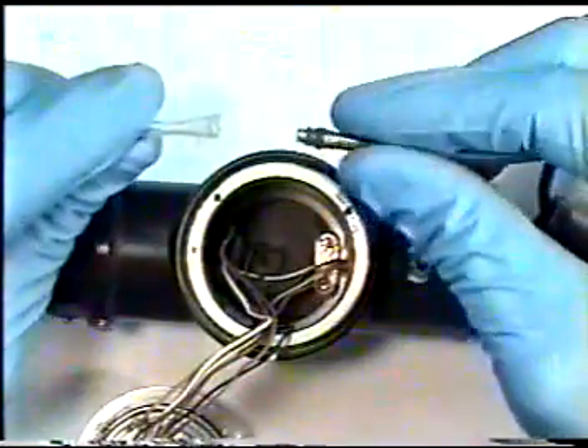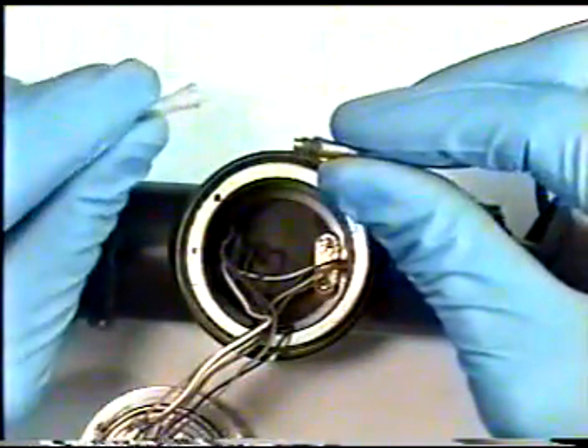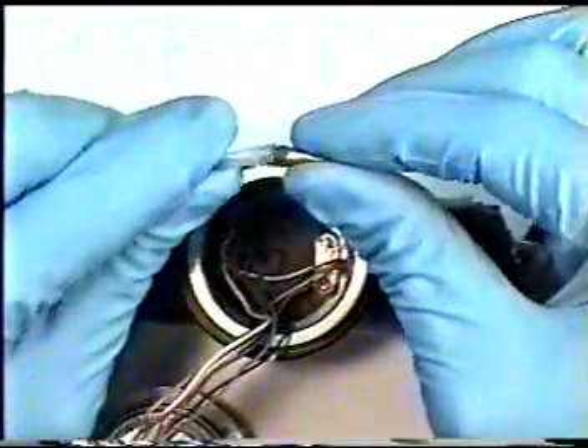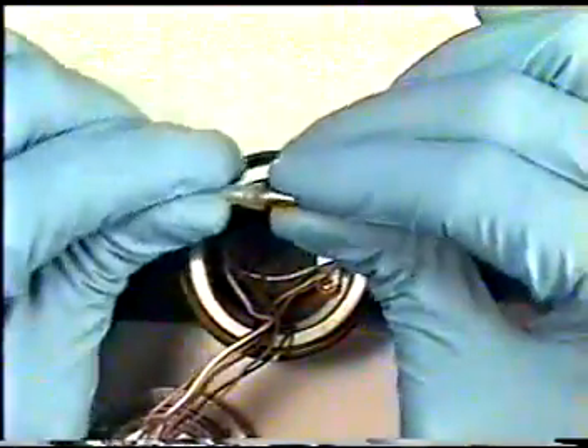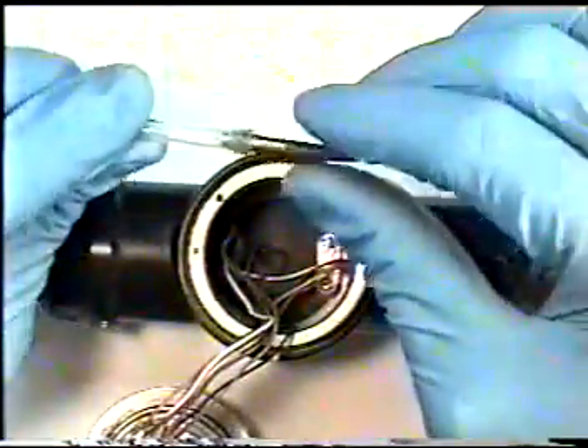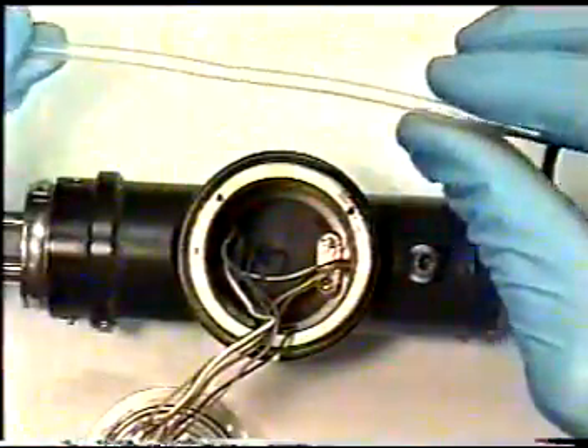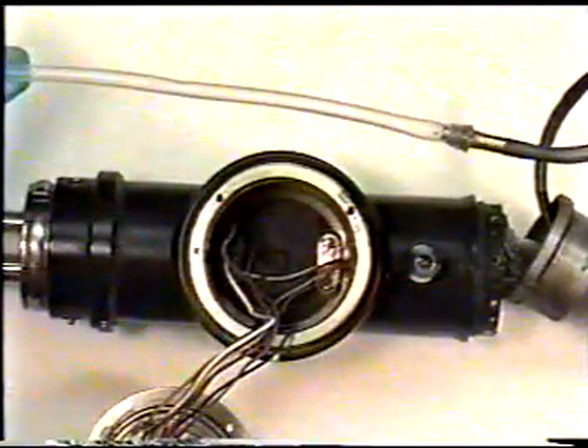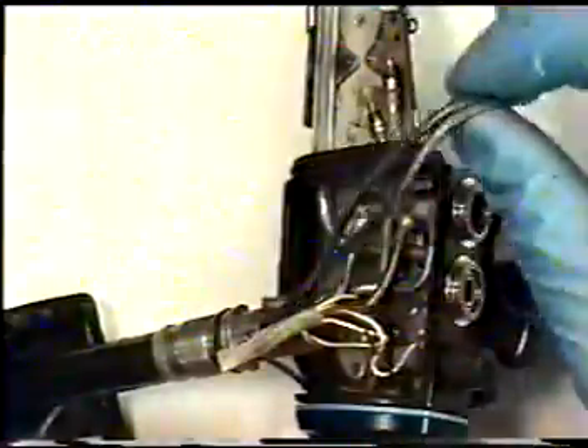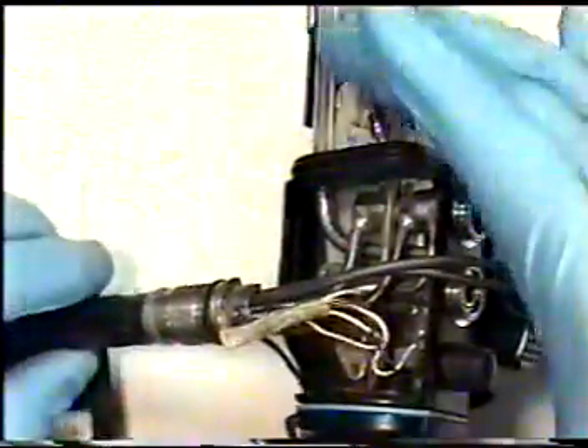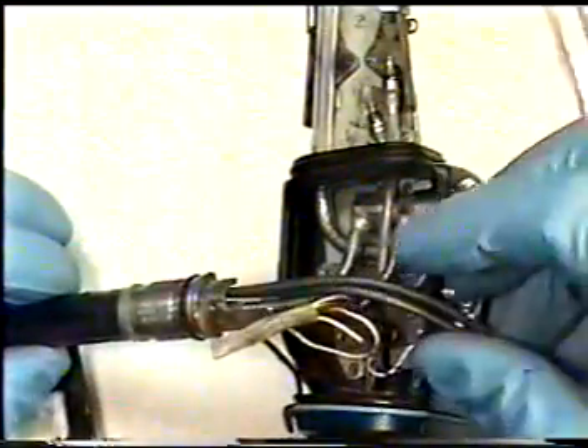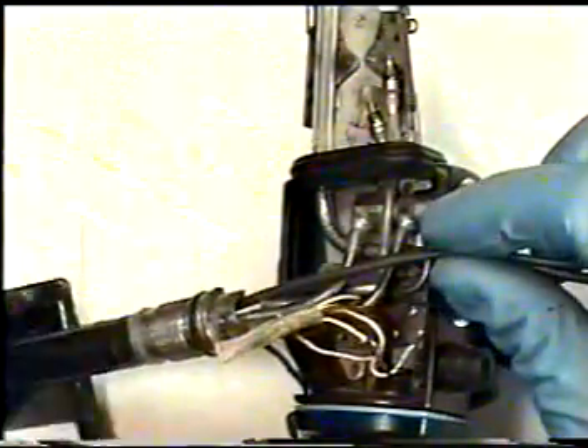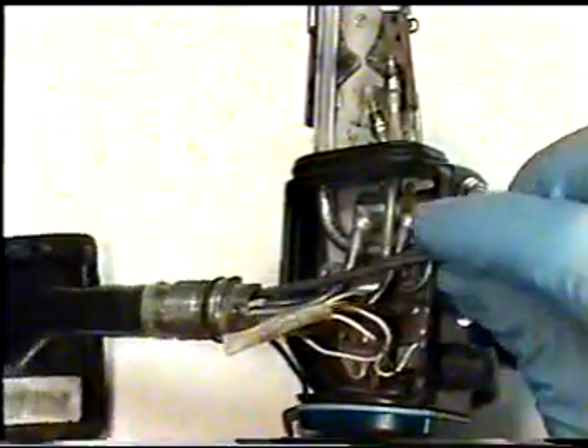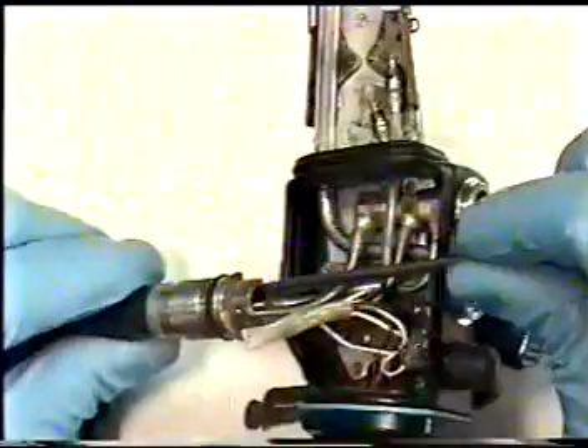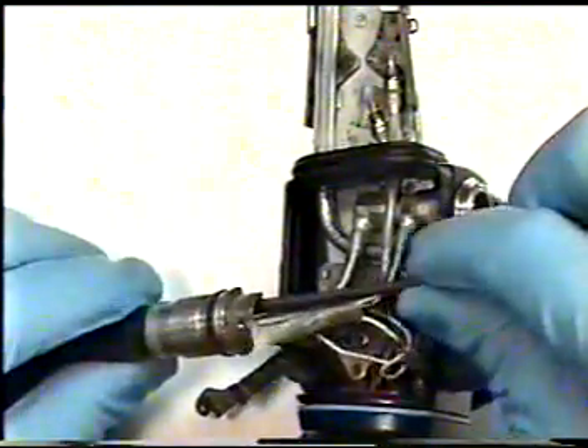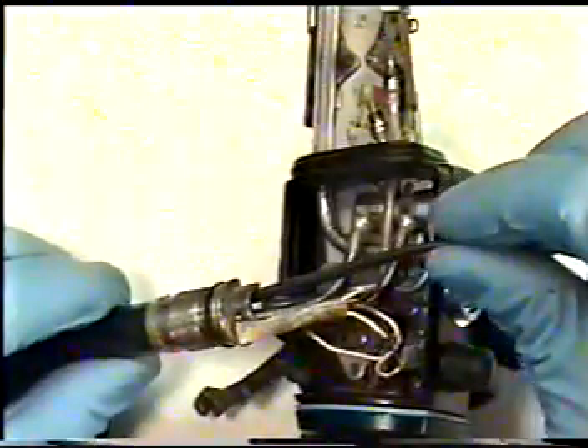Attach your larger plastic tubing over your light guide illumination bundle. You can actually use your old suction channel in order to fit over your light guide illumination bundle to pull through, so you can pull back through your new illumination light guide bundle. Going back to our control section, we will now pull through our old damaged light guide bundle. Lay the endoscope in again in a 90-degree angle so we can pull through our light guide bundles, making sure our light guide tube is straight along your working area. Pull through the old damaged light guide bundle along with your plastic tubing.